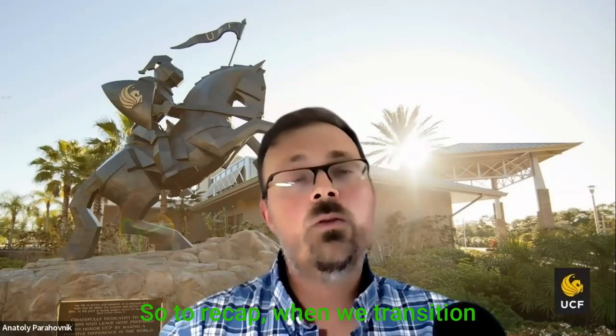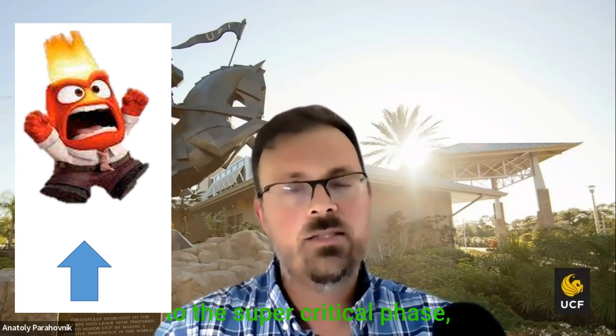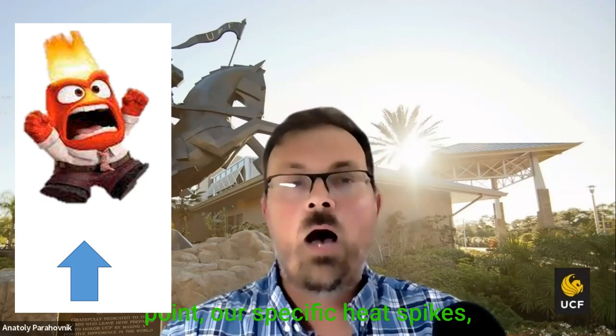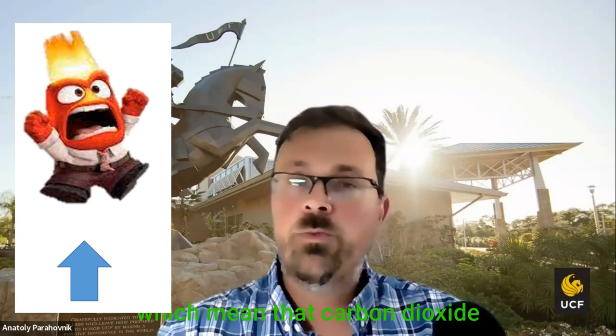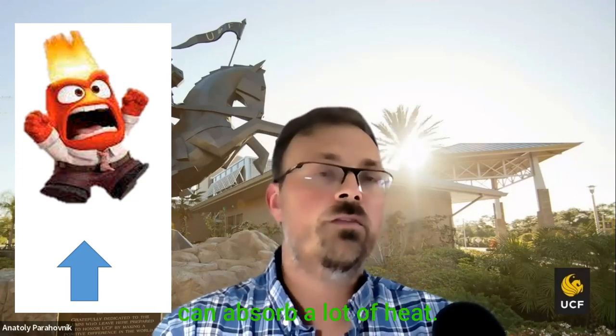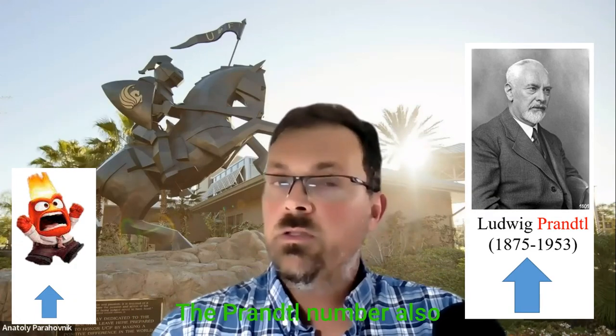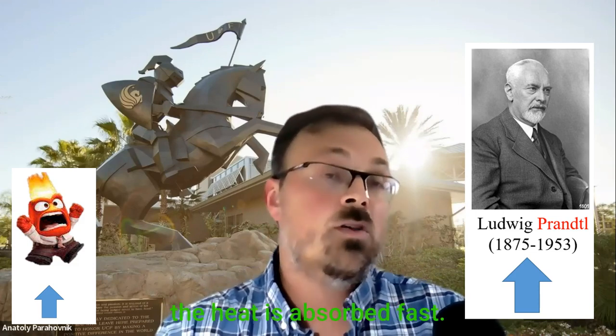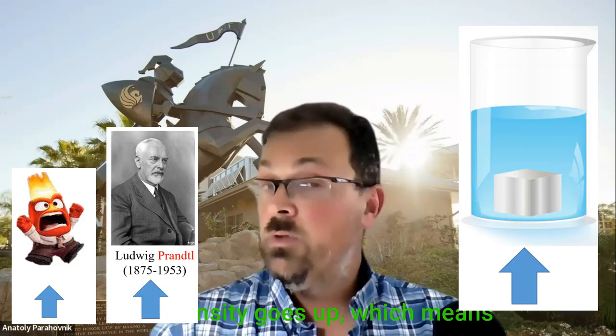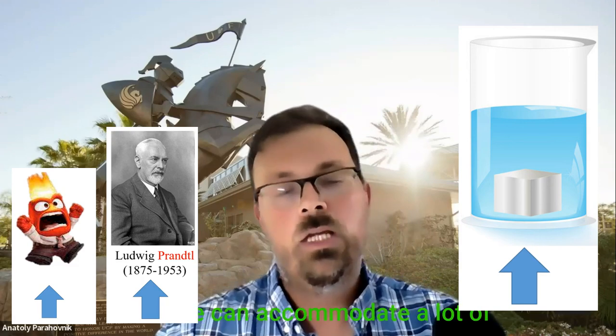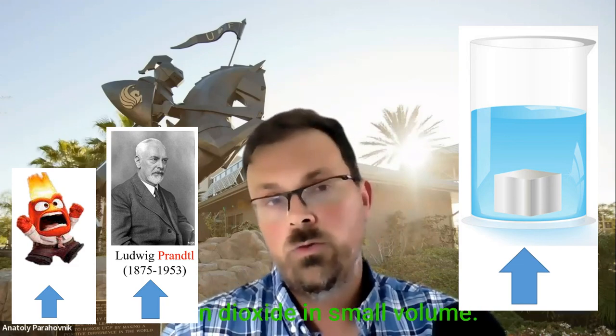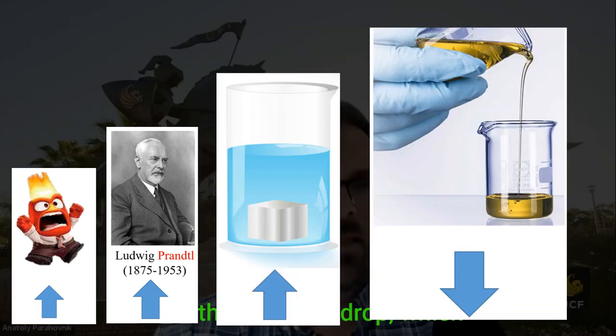To recap: when we transition to the supercritical phase, especially around the critical point, specific heat spikes, meaning carbon dioxide can absorb a lot of heat. The Prandtl number also spikes, meaning heat is absorbed fast. Density goes up, meaning we can accommodate a lot of carbon dioxide in a small volume so the system becomes smaller. And viscosity drops, meaning we don't need high power to circulate carbon dioxide in the system.